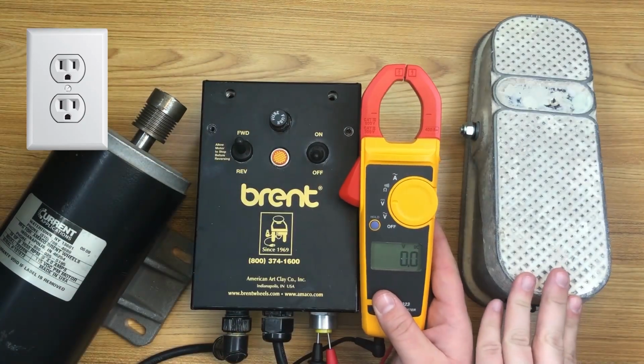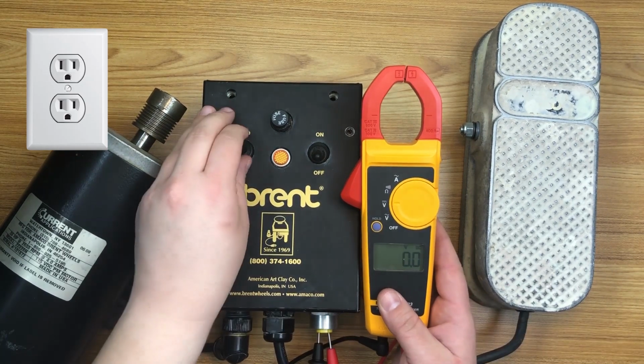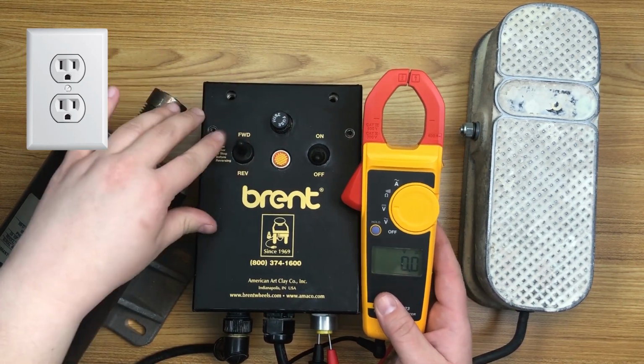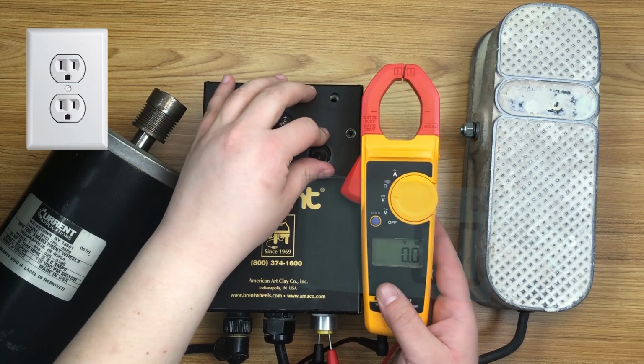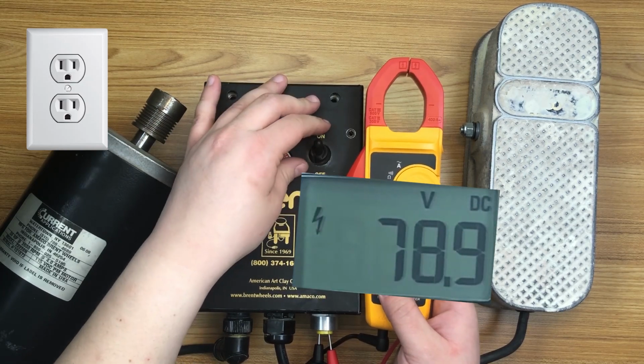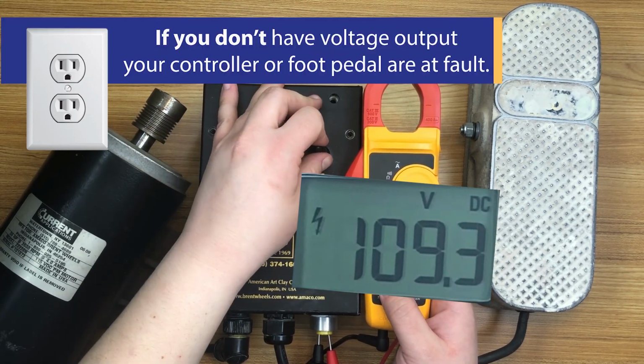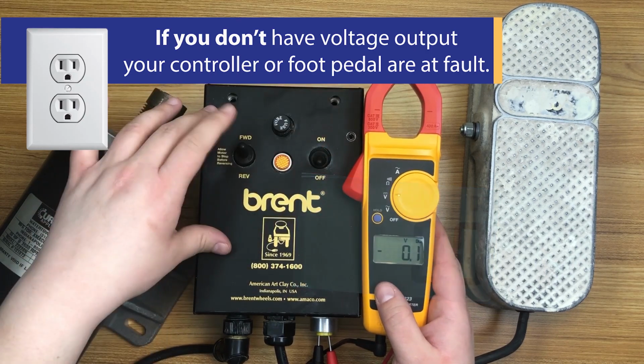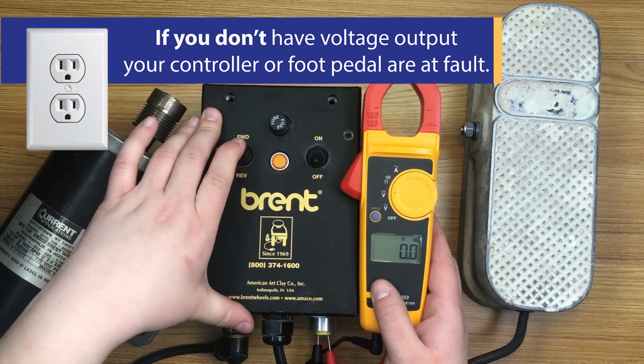Make sure your foot pedal is engaged. Place the controller in the forward position and turn the controller switch on. Your direct current voltage should read somewhere around 100. Repeat this with the controller switch in the reverse position, and you should see a similar number in the negative.